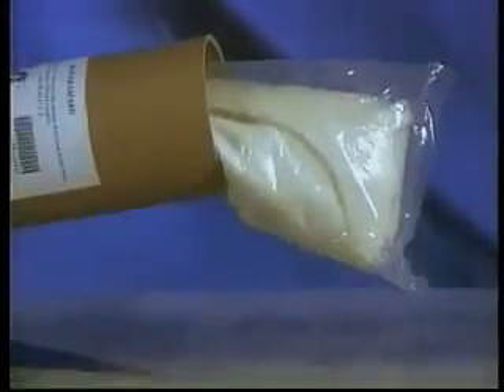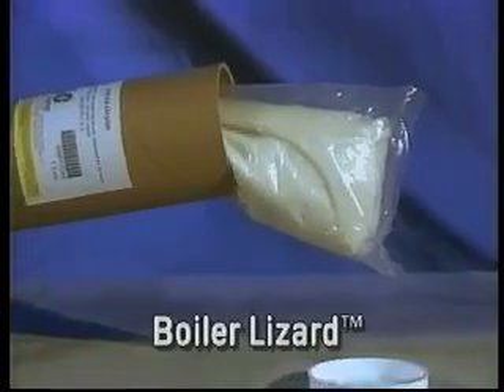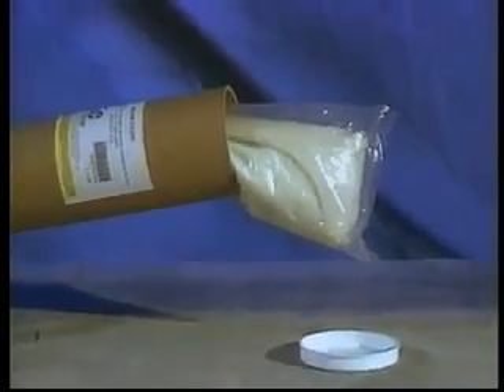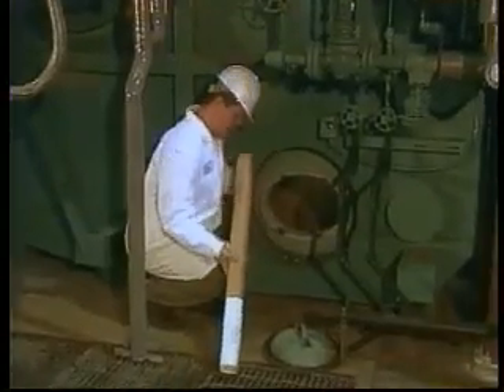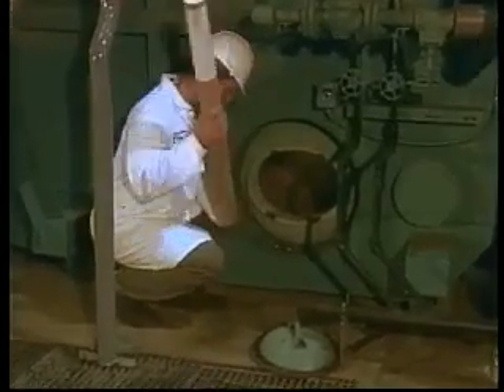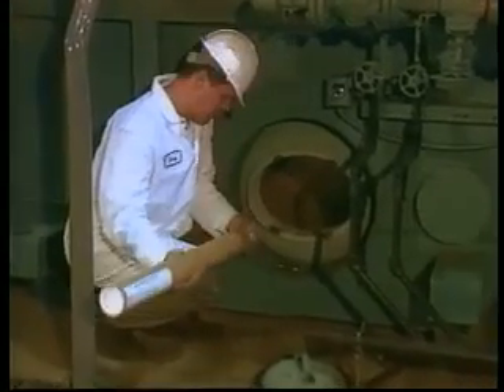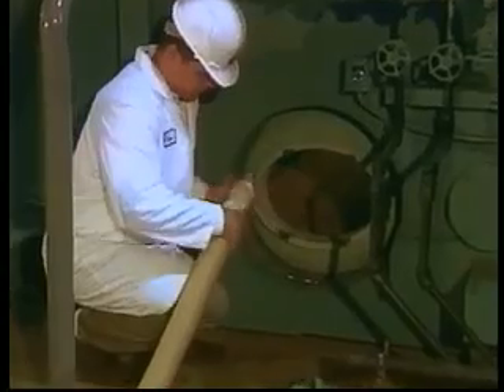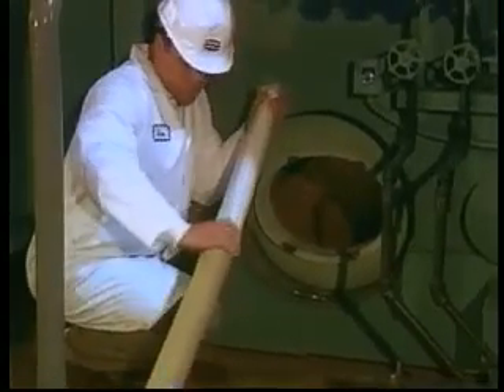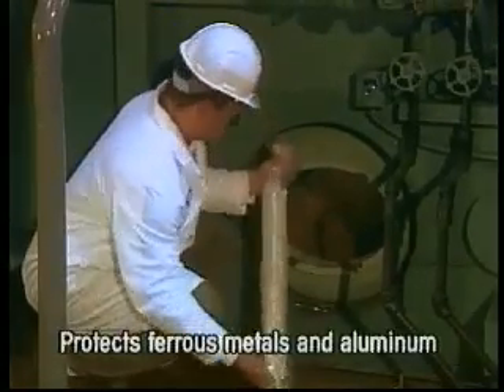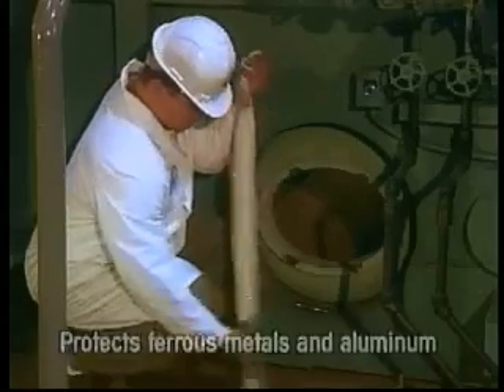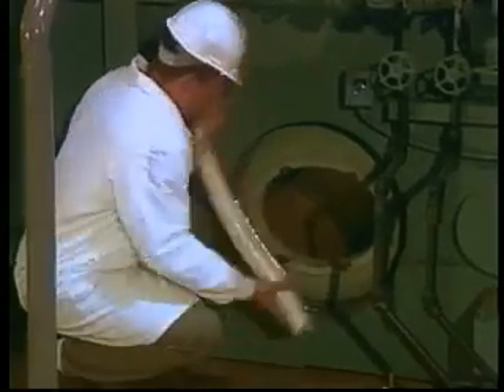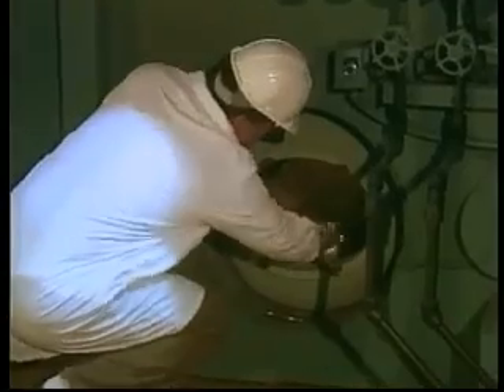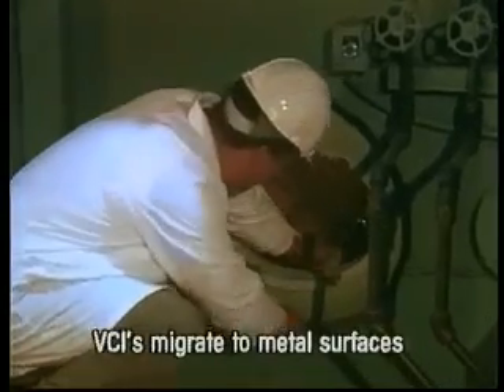The first product in Cortec's layup line is the Boiler Lizard, designed especially for dry layup and shutdown of boilers. The Lizard includes VCI powder packaged in a water-soluble polyvinyl alcohol bag. Lizards prevent corrosion on ferrous metals and aluminum in enclosed spaces. Just add one to the enclosure and slit open. Then seal all the openings, and the VCIs in the Boiler Lizard will migrate to protect all metal surfaces.